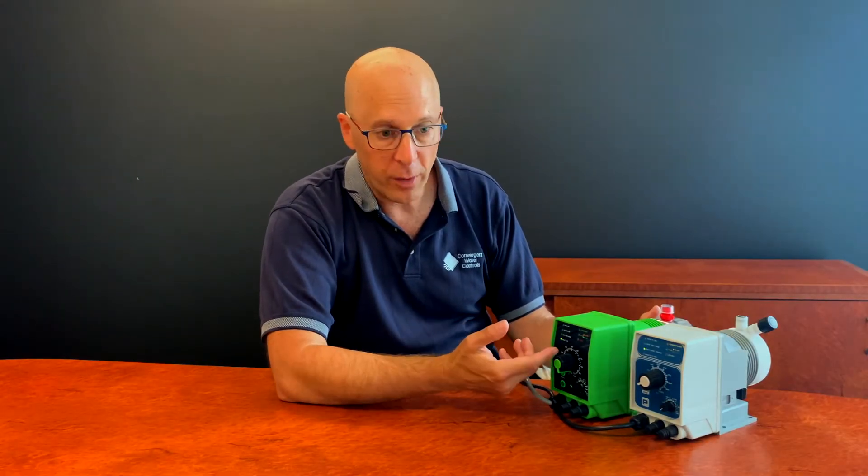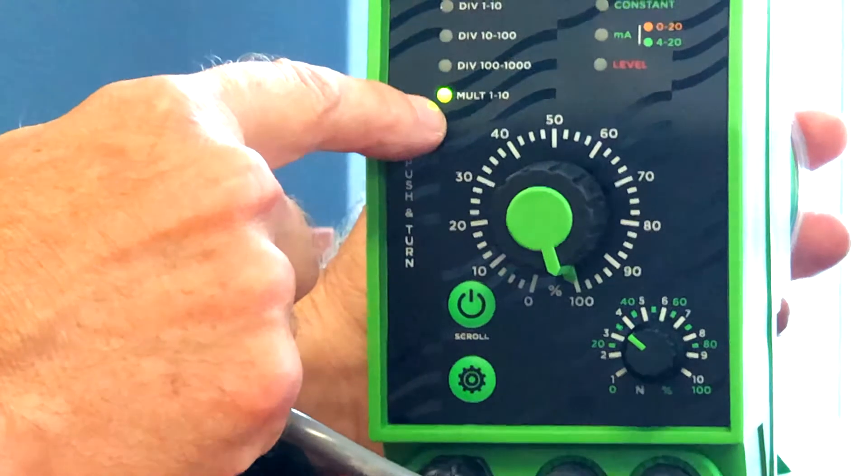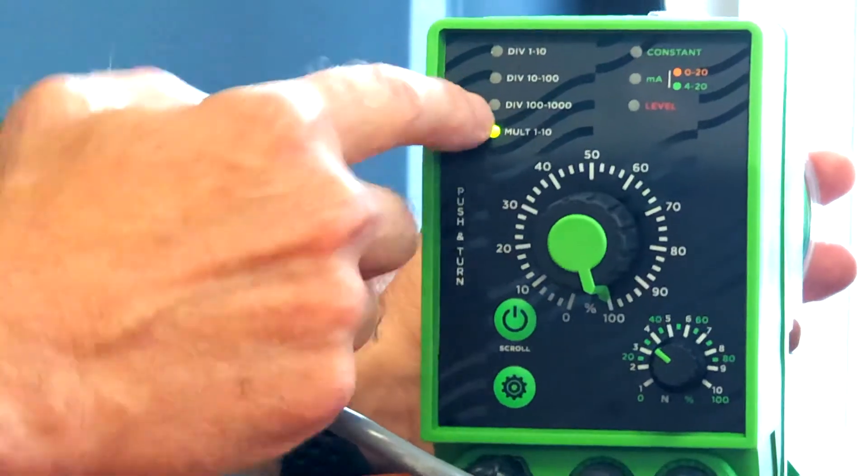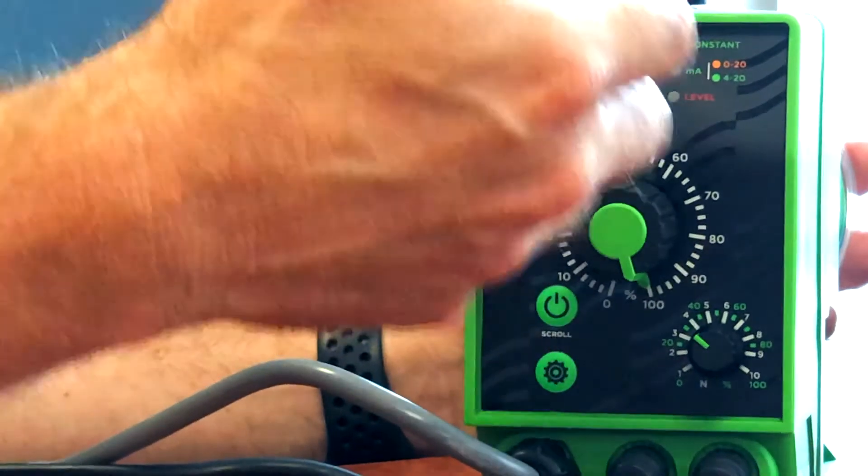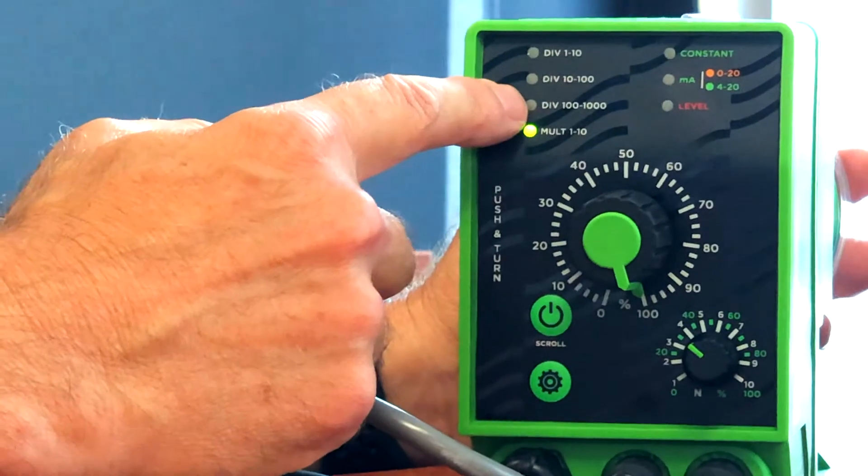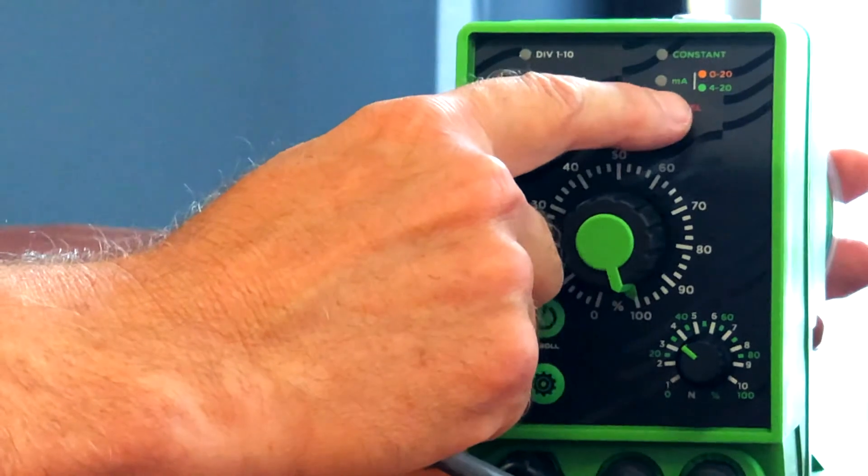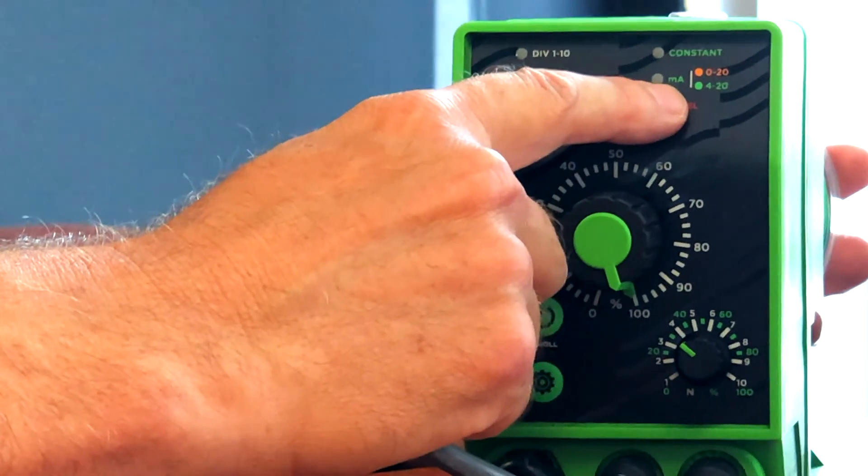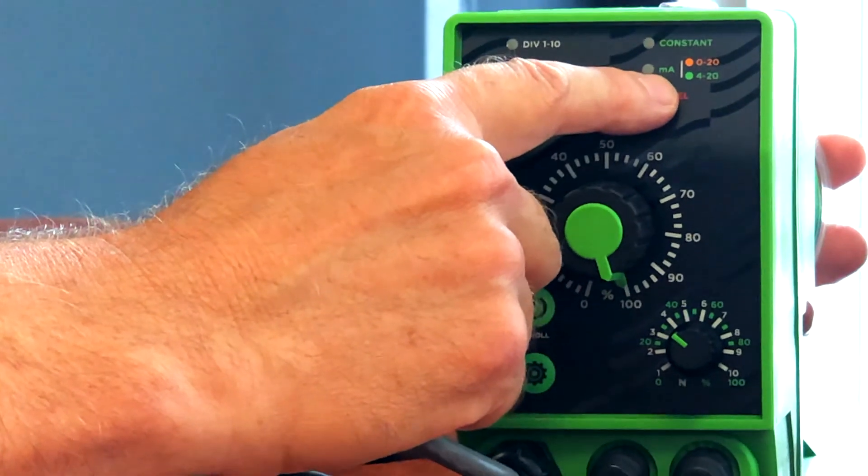The other modes that we have are multiply 1 to 10. We also have dividing modes, which means that you have to receive a number of pulses before you give one stroke. The pump can also dose proportional to an external milliamp signal, which can be 4 to 20 milliamp or 0 to 20 milliamp.